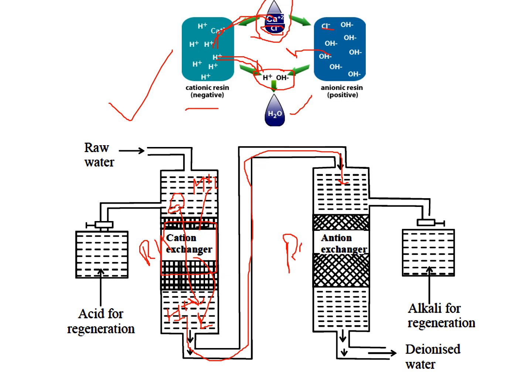This water is then passed into the second vertical tank, which contains the anion exchange resin. The anion exchange resin has a number of OH⁻ ions. All anions are replaced by OH⁻ ions — for example, if one Cl⁻ is captured by the anion exchange resin, one OH⁻ is released into the water. The H⁺ ions and OH⁻ ions then combine with each other.